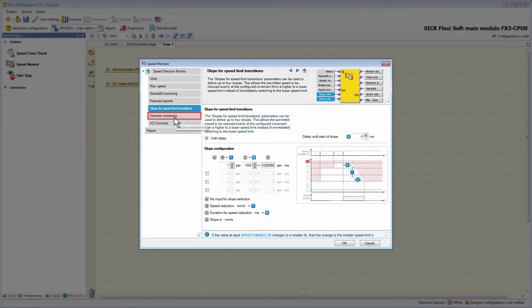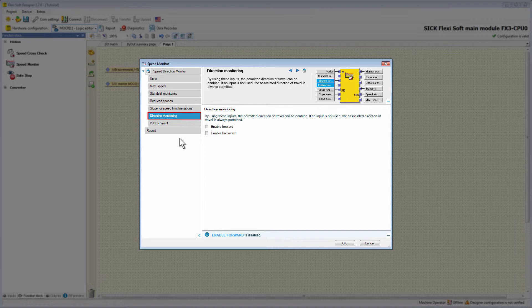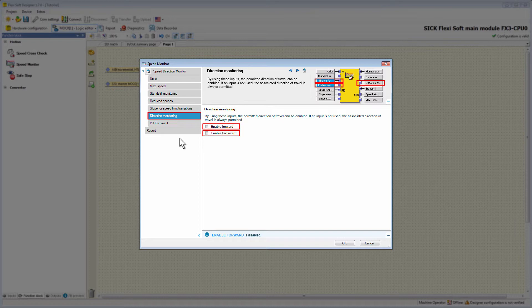Moving on to the tab Direction Monitoring, here it is possible to activate the optional inputs Enable Forward and Enable Backward. Using these inputs, the permitted direction of travel can be enabled. If an input isn't used, the associated direction of travel is always permitted. The output DirectionStatus indicates the direction: if the direction of travel is positive, DirectionStatus has the value 0; if negative, the value is 1. If movement occurs in a non-permitted direction, the output MonitorStatus changes from high to low.